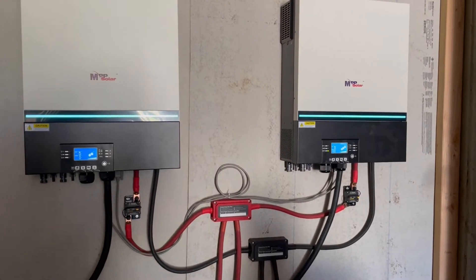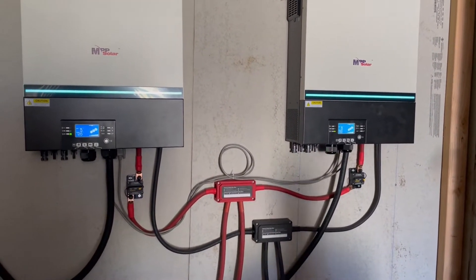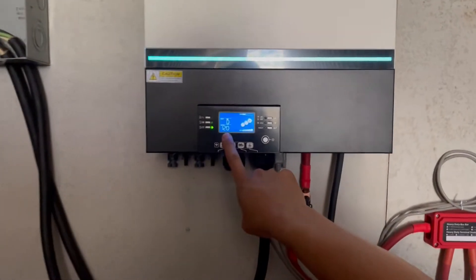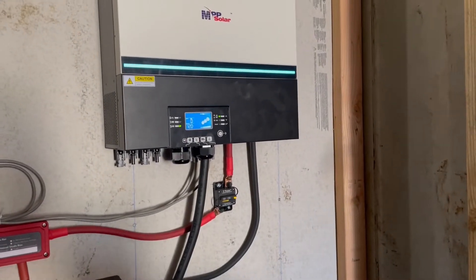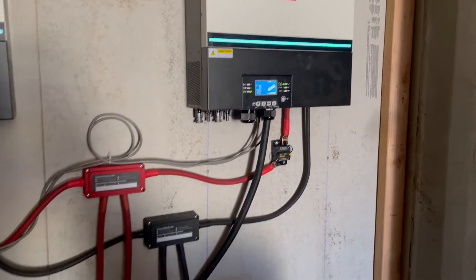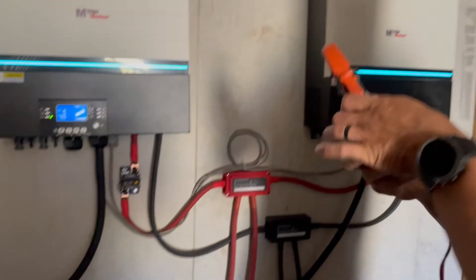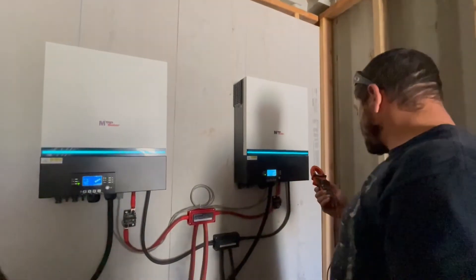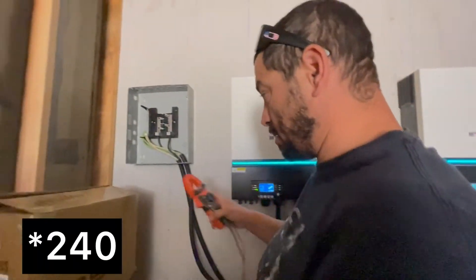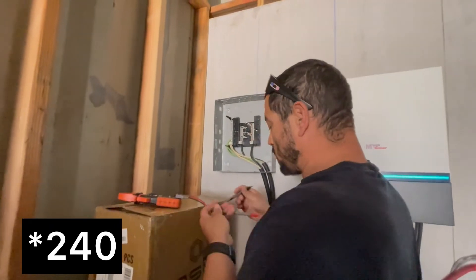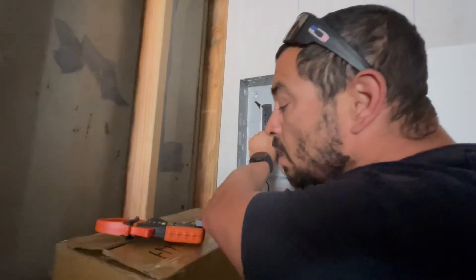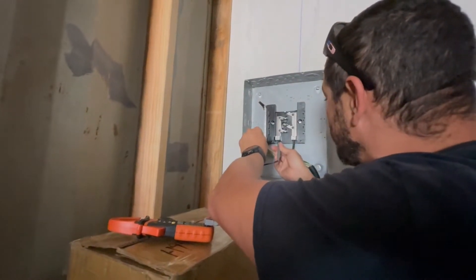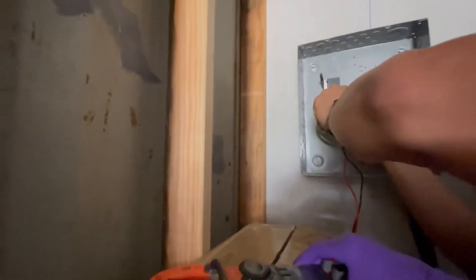So theoretically if everything's hooked up right we should get 120 on each inverter, which says 120 right there, says the same thing on this guy. I have them set up so it's in split phase, so theoretically now we should have 240 volt legs coming to this panel. Test the first leg, I get 119. If I test the second leg I get 119.